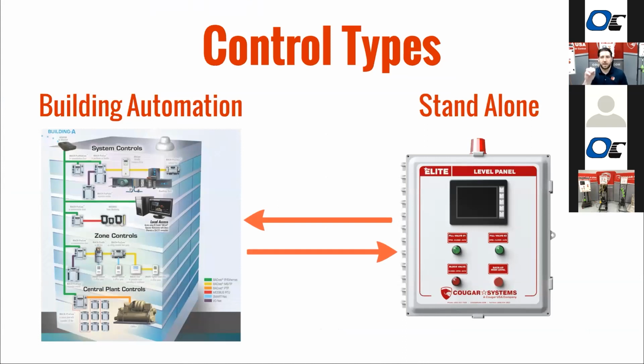So we're making that control panel that is specific to an application, meaning the design of it is geared specifically to whatever it's controlling. So that sump pump panel or that tank level panel that you see there has features specifically for that application, but we can communicate back to the building automation as well as receive information from the building automation to do remote enable, disable, set point rollbacks, things like that.